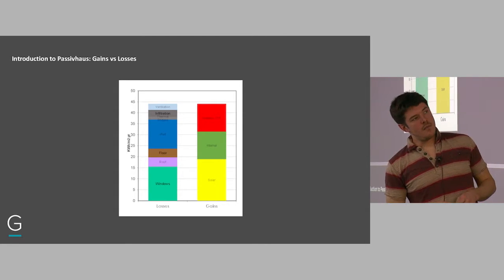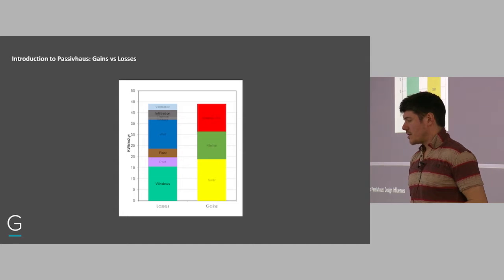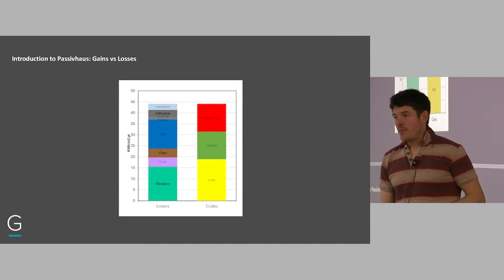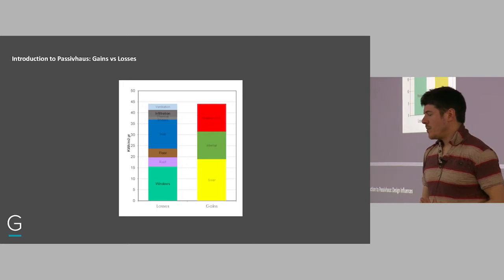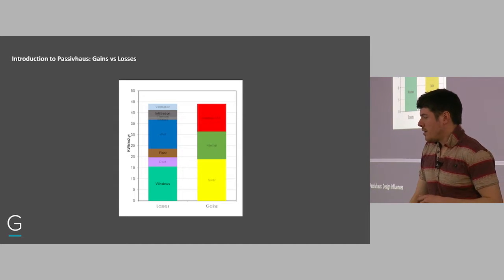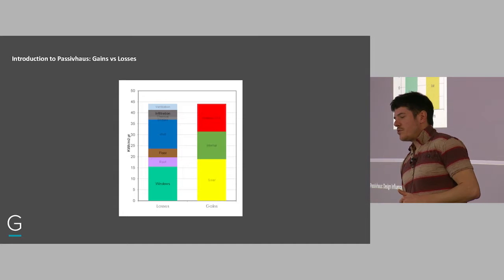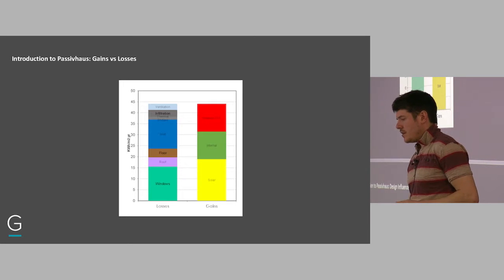And then on the left, we've got a breakdown of all the heat losses. On this particular project, there's quite a lot through the walls and quite a lot through the windows. But we can see we've reduced the heat losses through ventilation by using our MVHR. The infiltration losses, that's the air leakage from the building, are pretty small as well. There's a little bit left in there for thermal bridging, and the walls and the floor and the roof are pretty good. So that's a fairly typical kind of graph. And you can see our 12.6 on there is below our 15, so that's all good.